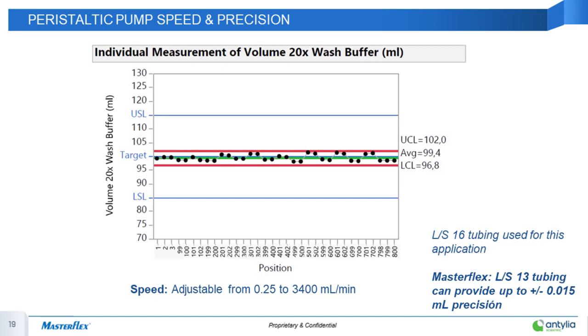We could do it even faster, but as the reagent we dispense creates a lot of foam, we had to limit the flow rate to avoid that foam. As can be observed in the control chart in the image, good precision was maintained. It has just a small variability and widely meets our demand of a precision over 95%. The smallest tubes take less than a second to be filled, and good precision is also maintained. Another good point of the peristaltic pump is that the volume range is actually unlimited. It may vary in precision and finish time a little bit, but it can dispense almost any volume.